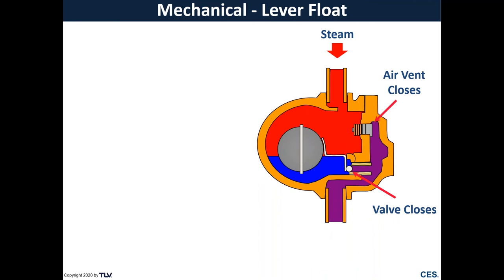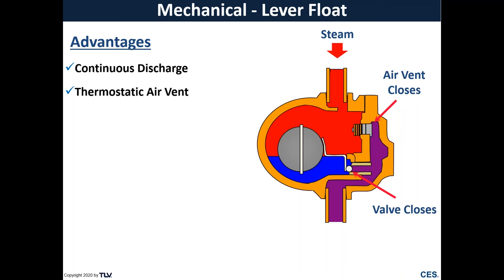And as our system heats up, the thermostatic element is going to close due to high temperatures. And then once we discharge all that condensate, that float and lever mechanism will then shut. Some advantages to the steam trap is it's more of a continuous discharge. So because this is a float floating on the liquid level, it will change based on what's coming in. As I mentioned, there is a thermostatic element, so this is very good at venting air. Because of its lever mechanism, it allows you to incorporate a larger orifice size, which then results in high capacities.